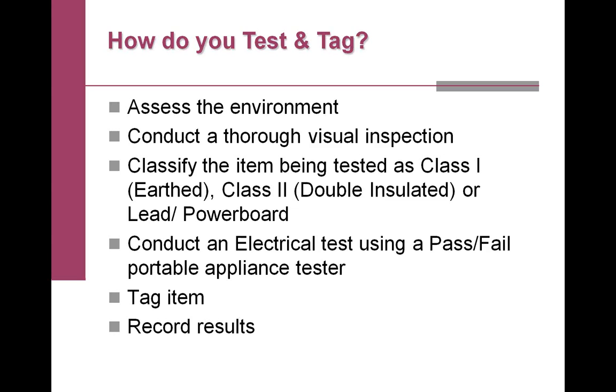In other words, they can't use an instrument that requires interpretation. An electrician, for instance, could use what we call an insulation tester to do certain parts of the testing, and that would provide them a reading of insulation resistance, but then you have to know the pass and fail rates by referring to the standard and make an interpretation of that reading as to whether it's safe for use. So a portable appliance tester takes all that guesswork out of it, and it simply gives them a pass or fail. But they must understand the process of classifying those items before they plug them in, and that's again part of the training. Once they've done that, they tag the item.